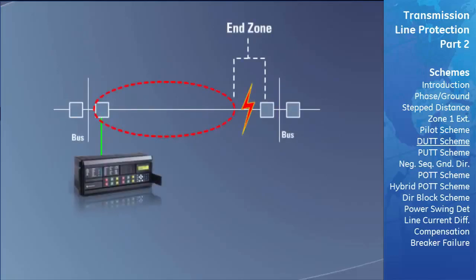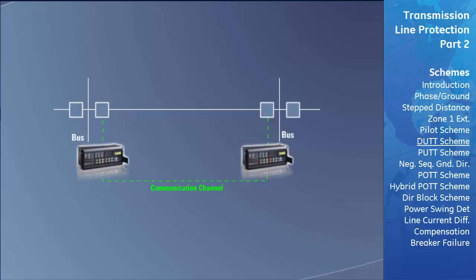A fault in the end zone of a transmission line normally will not be fully cleared until the Zone 2 time delay expires. The DUTT scheme—Direct Underreaching Transfer Trip—reduces the time needed to clear such a fault. A communication channel must be set up between the distance relays at each end of the line. This channel may have the ability to send only one bit of data, such as a power line carrier link, or multiple pieces of data, such as a fiber optic or microwave link.